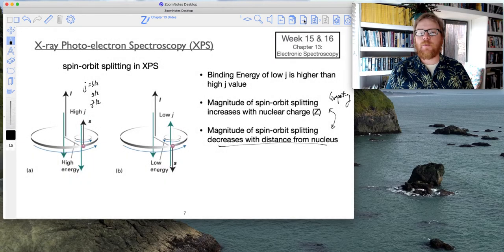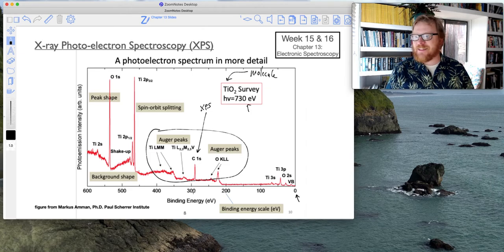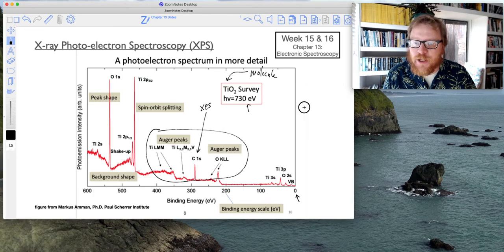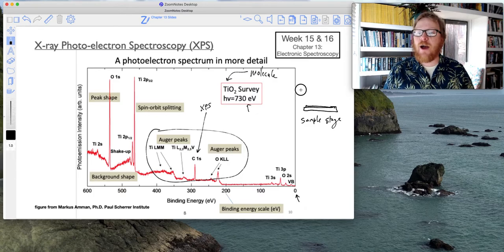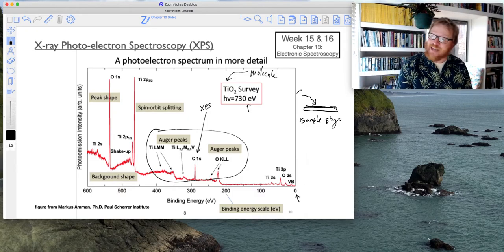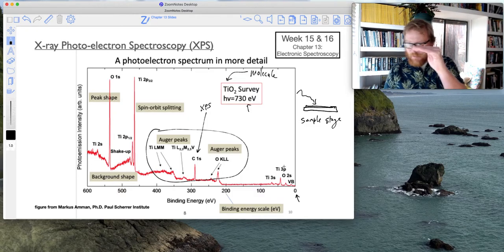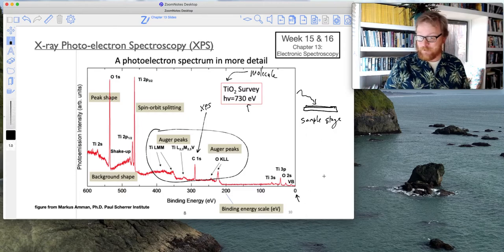So why would there be carbon in this sample? The answer is because when you put your sample on the manipulator stage, I'll just call it the sample stage, and here is our analyte, every now and again the XPS technique can sample some of the elements on the sample stage if you haven't manipulated it perfectly, okay?